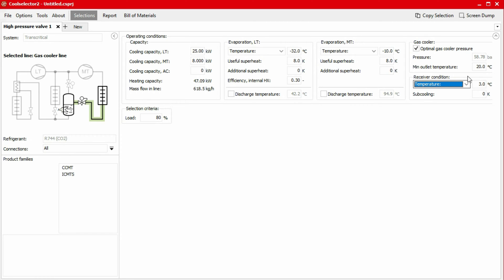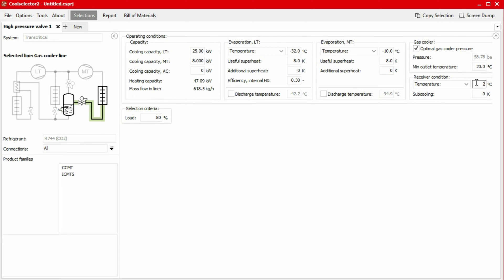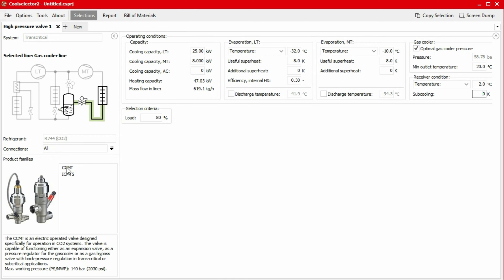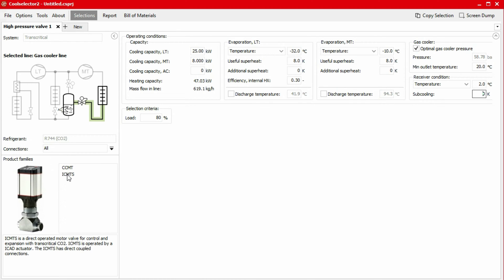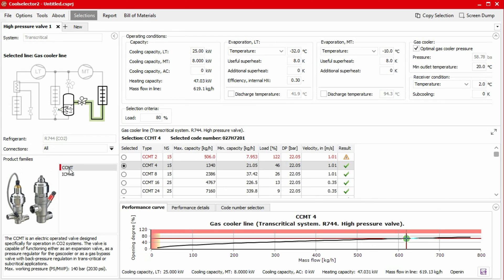There are two options available for the receiver conditions: the pressure or the saturation temperature. In this example, we'll specify a temperature of 2 degrees Celsius. We can then set our selection criteria based on load. The application will suggest products which best match the operating conditions and load percent. For this example, we'll leave it as 80%. In the product family section, the products which are compatible with the system definition are displayed. We can hover our mouse over the product title to display a product photo as well as a brief description. For this example, we'll select the CCMT valve.